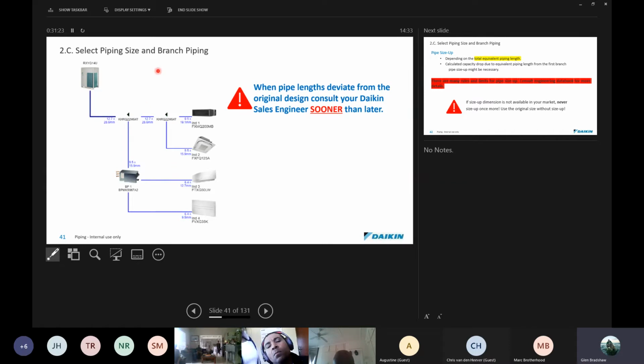So very important from an installer's perspective that you keep these piping lengths up to date. Don't wait to the end to find out that you've overshot and that you now have to change pipe sizes. That's going to cost a lot of money. You should have a pretty good idea, if you've done all your planning, what your actual piping lengths are going to be, because by the time you get to lay your piping, you've probably put down your cable tray, and even just measuring that would give you a pretty good idea where they're going to be. Okay.